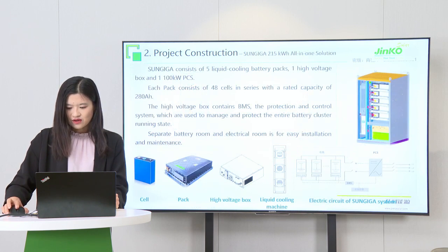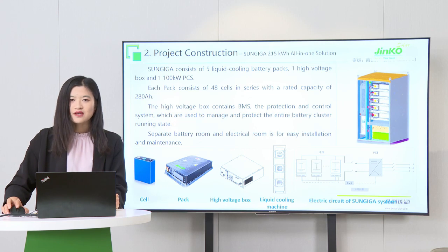Let's see the design details of the SUNGIGA all-in-one liquid cooling solution here. It consists of 5 liquid cooling battery packs, 1 high voltage box, 1 100 kilowatt PCS, and 1 4 kilowatt liquid cooling machine. Each pack consists of 48 cells in series with a rated capacity of 280 ampere hour. The high voltage box contains the BMS, the protection and control system, which are used to manage and protect the entire battery cluster running state. The separate battery room and electric room are for easy installation and maintenance.